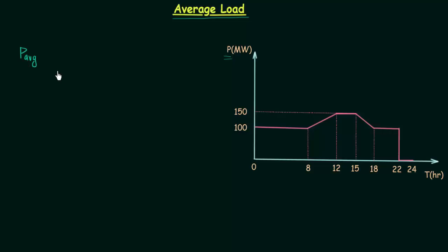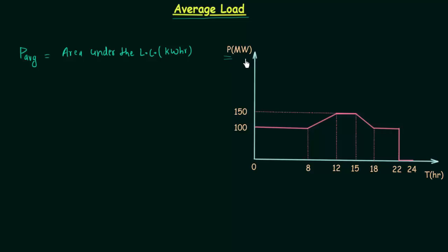P_AVG is the representation of average load and it is equal to the area under the load curve in kilowatt hours — or if power is given in megawatts, then it will be megawatt hours — divided by the total time. The unit of time is hours, and the total time is equal to 24 hours in this case.